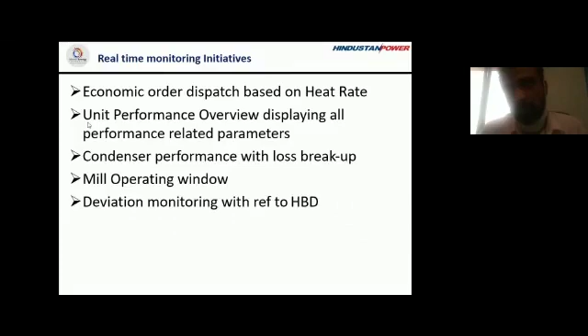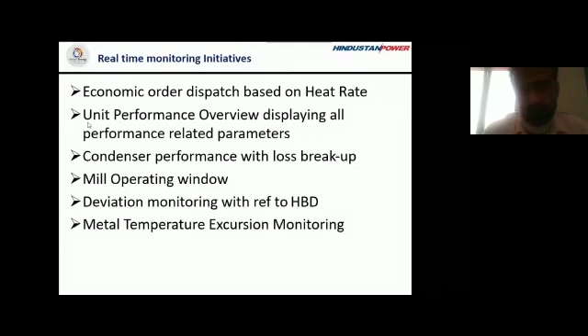We dynamically monitor deviation as compared to the HBD, and since our HBDs were given only for 5 load conditions starting from 40% to 100%, we have again used data science to generate an intermediate value for the rest of the load conditions to derive all the 4 parameters mentioned in HBD. And we have, on a day basis, metal temperature excursion monitoring.